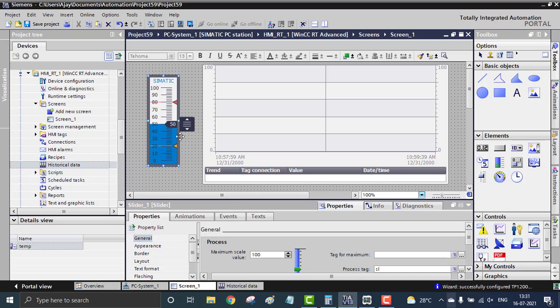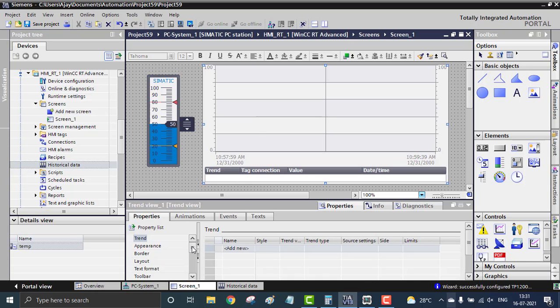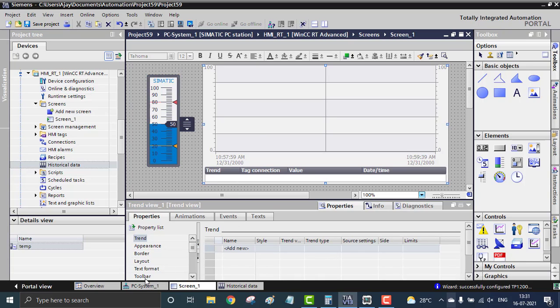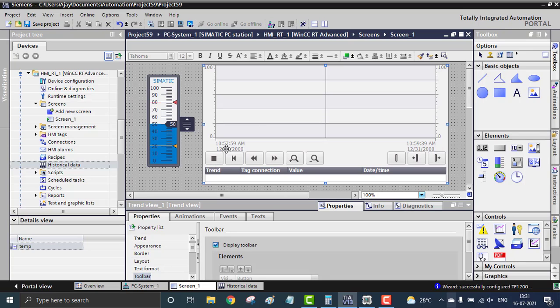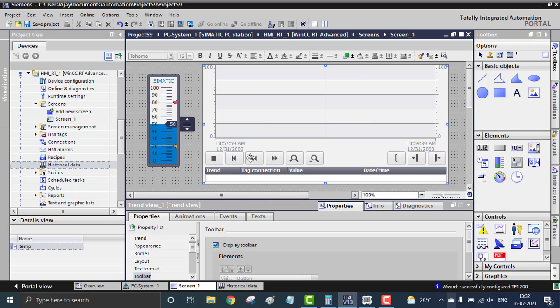Now I'm back to my screen to develop the other things. By changing the slider I can simulate my temperature varying. I also need to add a toolbar — inside the toolbar I have to display the toolbar for historical logging. I have to refresh the trend view manually, because unlike a real-time trend, the historical trend won't show values continuously without refreshing.